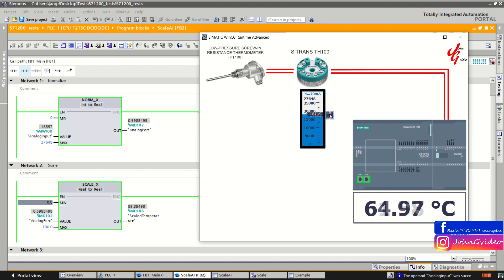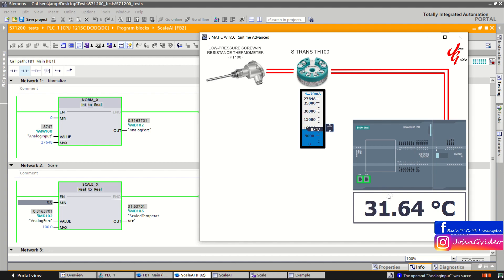As you can see, when the value is bigger the temperature is also bigger, and when it is lower the temperature is also lower. This scaling can be used for any other types of analog inputs as well — for example voltage analog input from 0 to 10 volts, or from 0 to 20mA if you have a current analog input. You can also use these function blocks for analog output in a similar way.